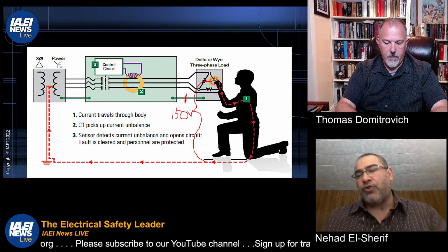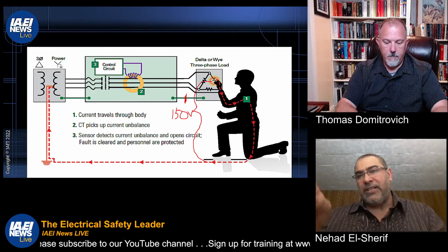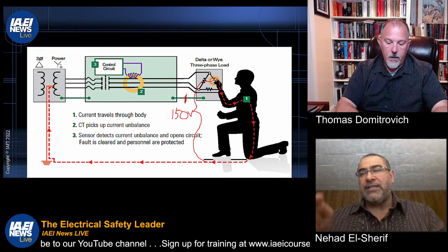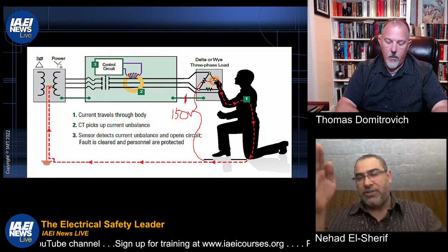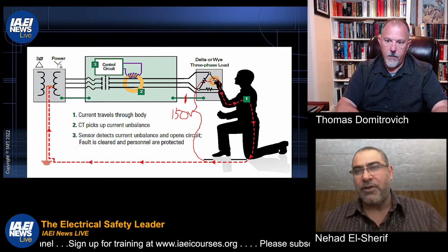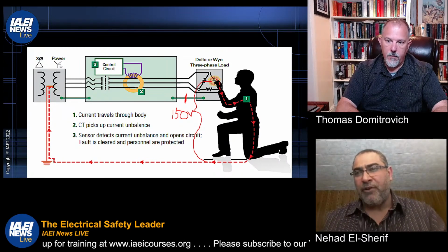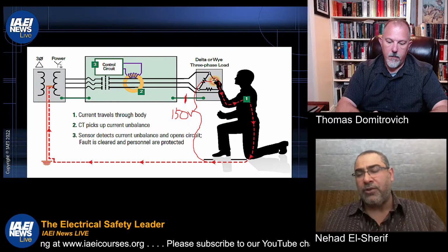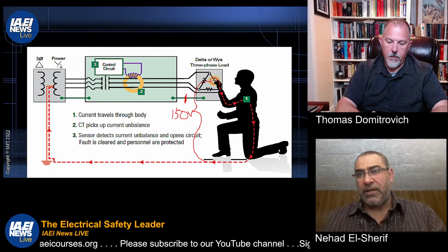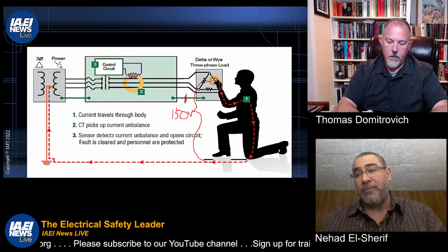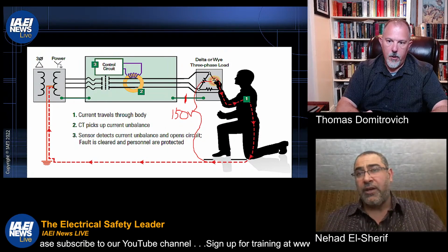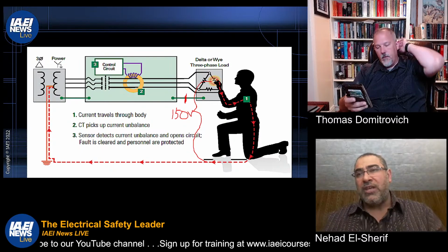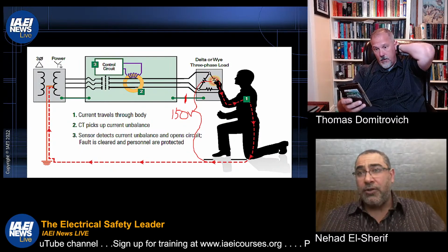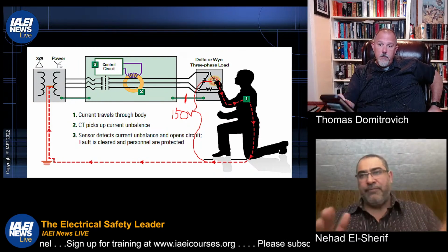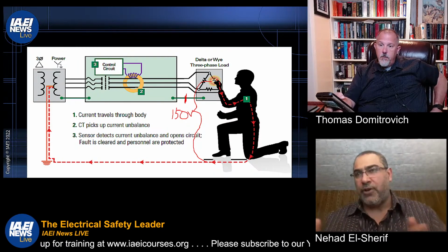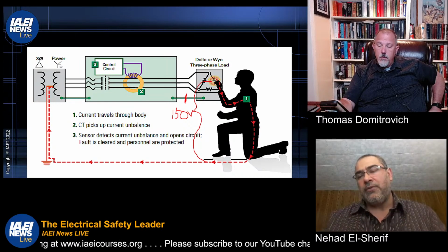The equipment grounding conductor's role is, don't forget, it will be connected from the equipment to the ground, which is in parallel to the person, right? I know it's not on the figure that Tom is showing, but just think of how equipment grounding conductors are connected. They're connected from the non-current-carrying metal parts of the equipment, like the chassis, all the metal parts not supposed to be current carrying, and it goes all the way to ground. So this equipment grounding conductor will be in parallel to the person, right? And based on Kirchhoff's current divider law, the higher impedance will get less current.